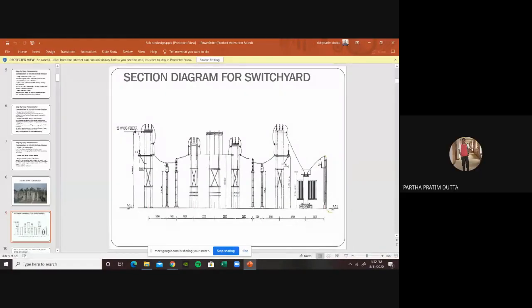And there is a CT, you see there is a current transformer, and there is a VCB, vacuum circuit breaker, already there. So current transformer and VCB, and then again a low level isolator is there for the low level bus, and then it is a bus supporter where the other bay can be connected through this bus supporter, and then again comes another isolator.